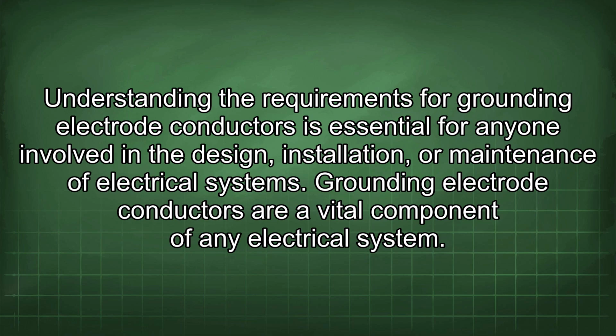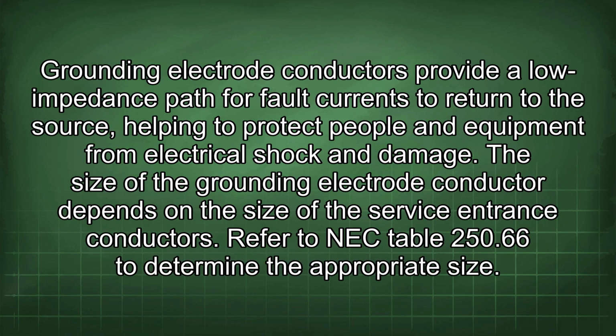Grounding electrode conductors are a vital component of any electrical system. Grounding electrode conductors provide a low impedance path for fault currents to return to the source, helping to protect people and equipment from electrical shock and damage. The size of the grounding electrode conductor depends on the size of the service entrance conductors. Refer to NEC Table 250.66 to determine the appropriate size.